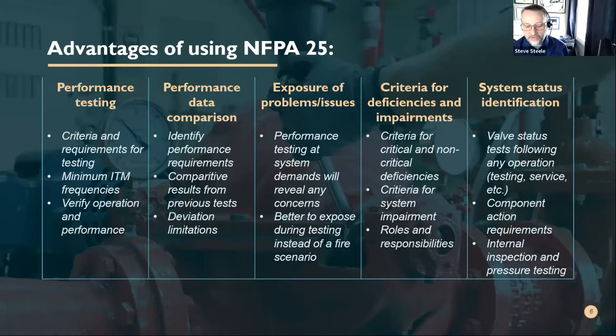From the time it takes to close the valve and open the valve, how can you guarantee that that is actually in the status that it was before, or even exposing a problem that the valve is either, you look at a butterfly valve where it is indicating that something happens where that valve doesn't open fully. There's something lodged in there that's now going to affect the performance. So there are some requirements in 25 that say once you do touch a system, there are checks that you have to do to ensure that the system is operable. It forces you now to do a performance analysis, however little it is. It might be that 2-inch main drain test. It might be additional servicing as far as lubricating the stem on an OS&Y. There are expectations.